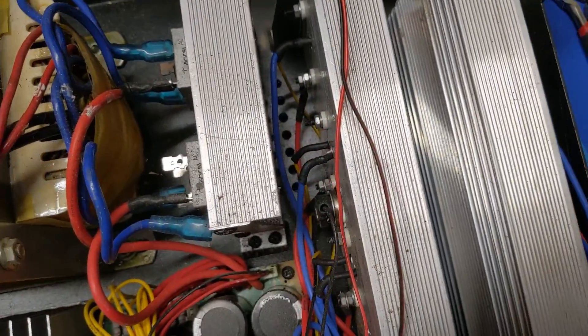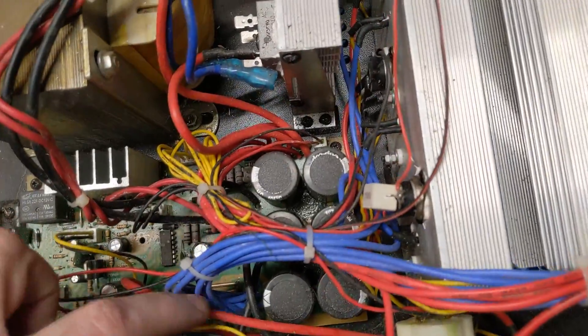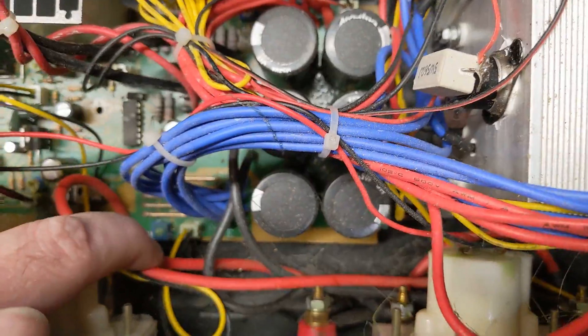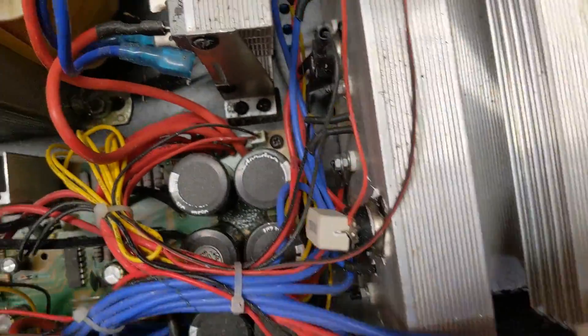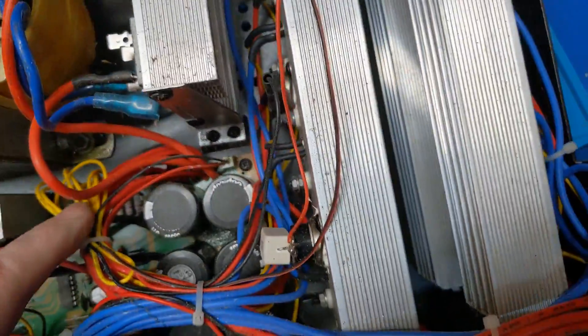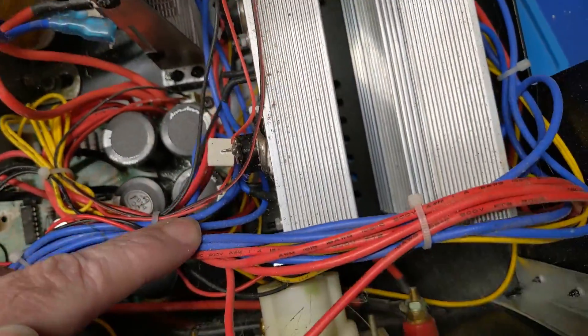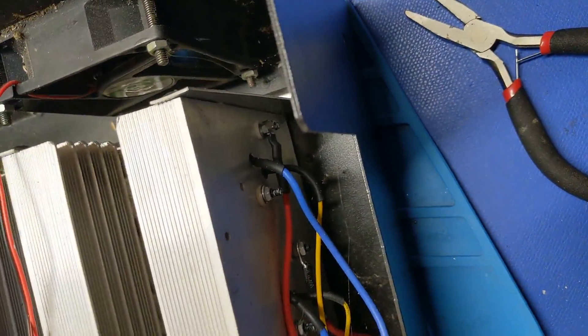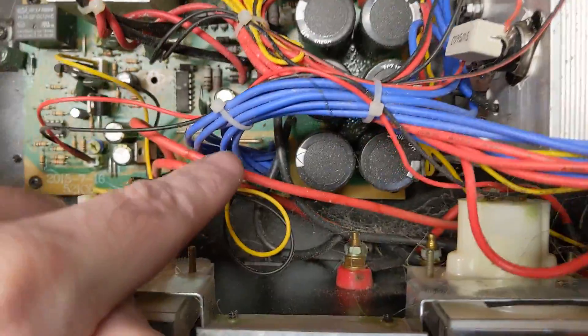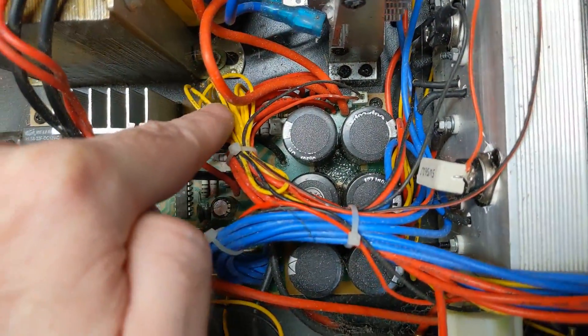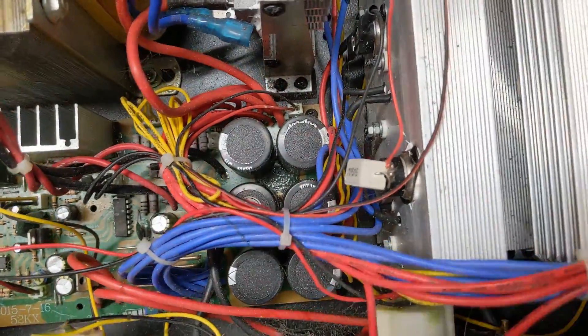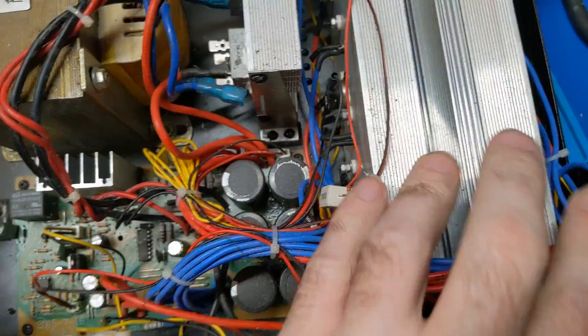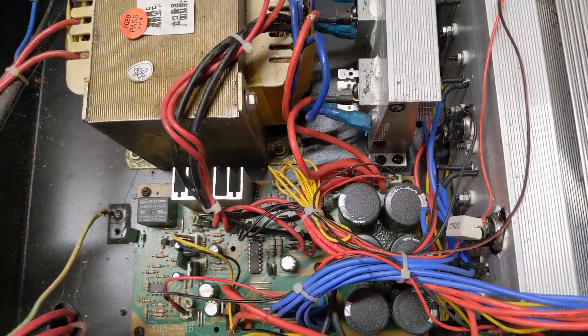Here's how you figure out if they're in parallel. What we do is we take the two positives here and we check them. Yeah, they're connected together. So yes, this winding is unhooked because otherwise it was just shorted together. But I don't have any shorts on the DC rails to ground, so that means everything upstream might be okay. I don't know, but might be okay. The next thing I want to do is check the transistor bank. All of these emitters are tied together. There's the emitter, there's the collector, there's the bases. So it looks like they're all in parallel. What we're going to do now is we're going to check the main transistor bank and make sure there's no shorts before we actually plug this thing in.